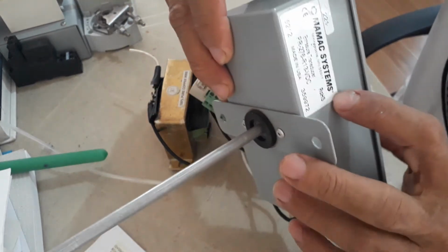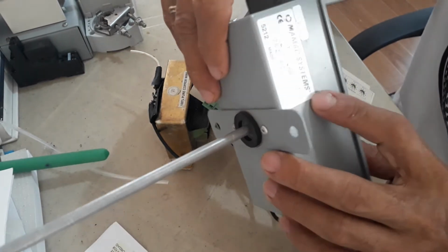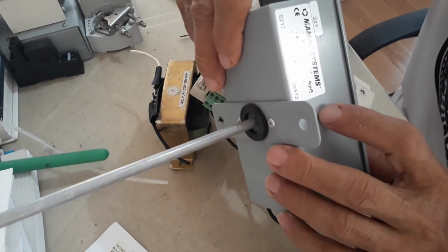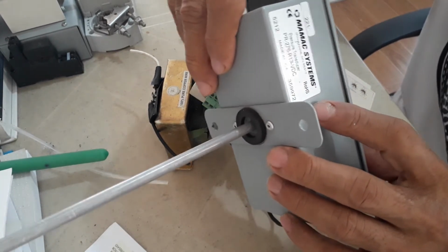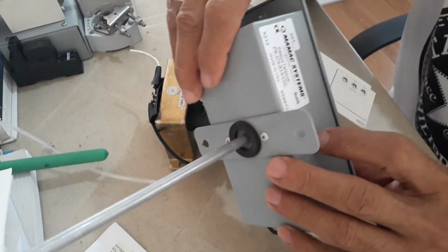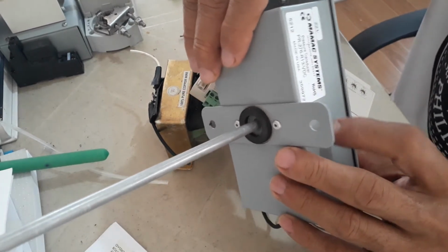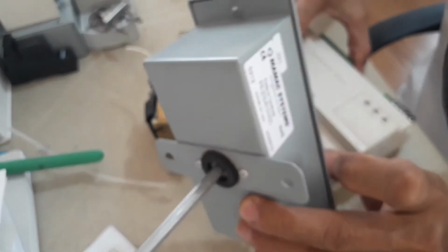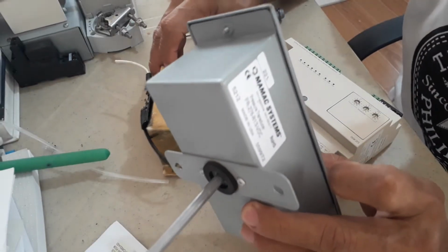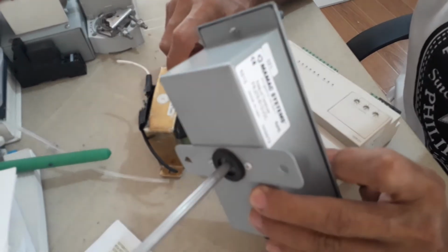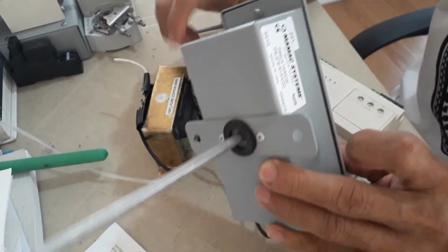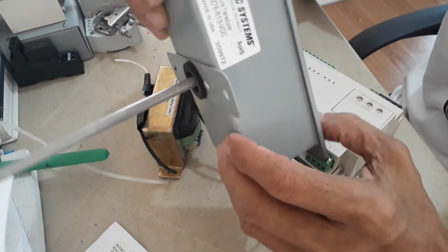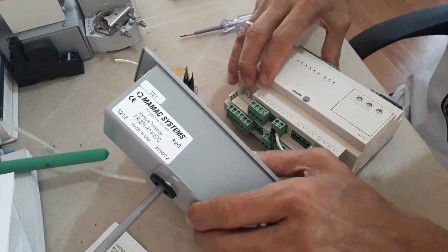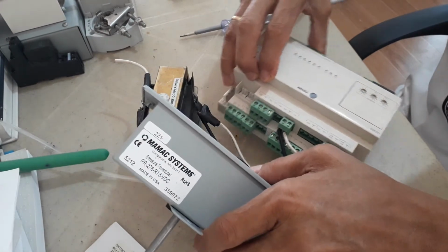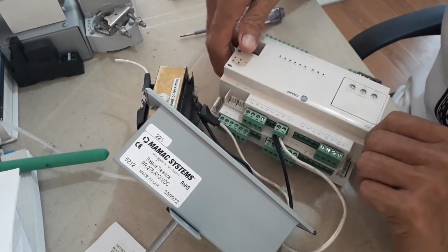The output of this sensor is 0 to 10 volts DC, and the power supply is 12 to 35 volts AC. Actually, what I'm providing is 24 volts AC, so it is within the range of the power supply requirement. Okay. Now I'm wiring this. So the output of this will be the input to my DDC.